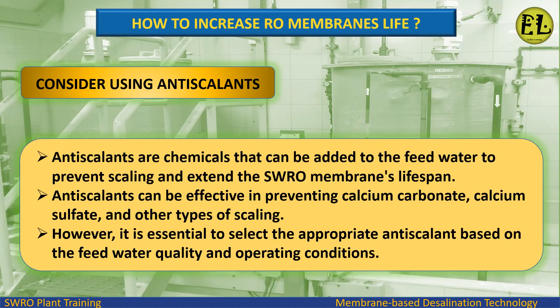Antiscalants are chemicals that can be added to the feed water to prevent scaling and extend the SWRO membrane's lifespan. Antiscalants can be effective in preventing calcium carbonate, calcium sulfate, and other types of scaling. However, it is essential to select the appropriate antiscalant based on the feed water quality and operating conditions.